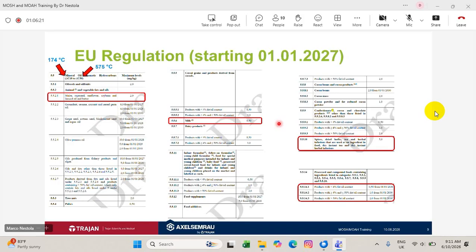Even when you have a lot of MOSH-MOAH in your chromatograms with a boiling point higher than 575 degrees, it's not considered. So the end is at C50, 575 degrees. Believe me, when you take normal products, there will be a lot of MOSH-MOAH higher than C50 at the very end of the chromatogram, sometimes even in the next chromatogram, because it's still on the column. But it's important to understand, because that question comes quite often. What about the MOSH-MOAH at the very, very end of the chromatogram?